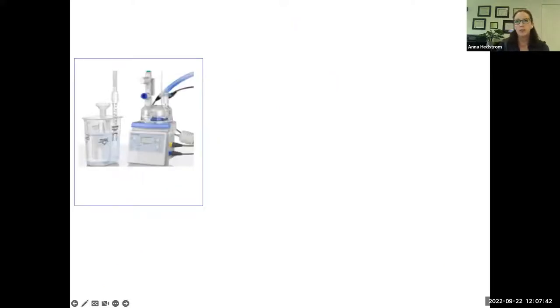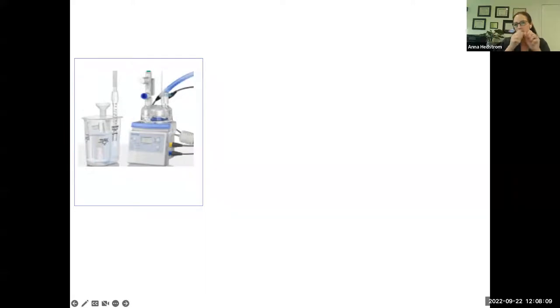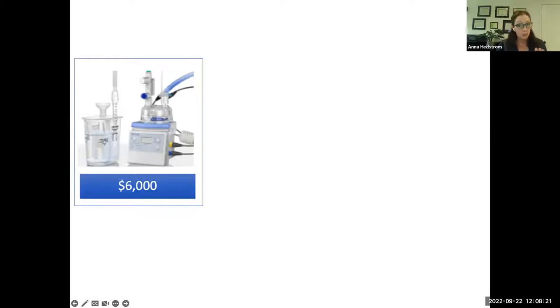This Fisher & Paykel bubble CPAP circuit might look familiar from your units. It has about $100 of disposable parts for every kid who goes on CPAP — when you put a 33-week kid who's grunting on CPAP, you open packages of equipment you'll throw away when they're done. The device itself, at the cheapest, is around $6,000 for bubble CPAP, and your units have many of these. It's obvious that price tag is not something most low-resource facilities can use to deliver CPAP to their babies.